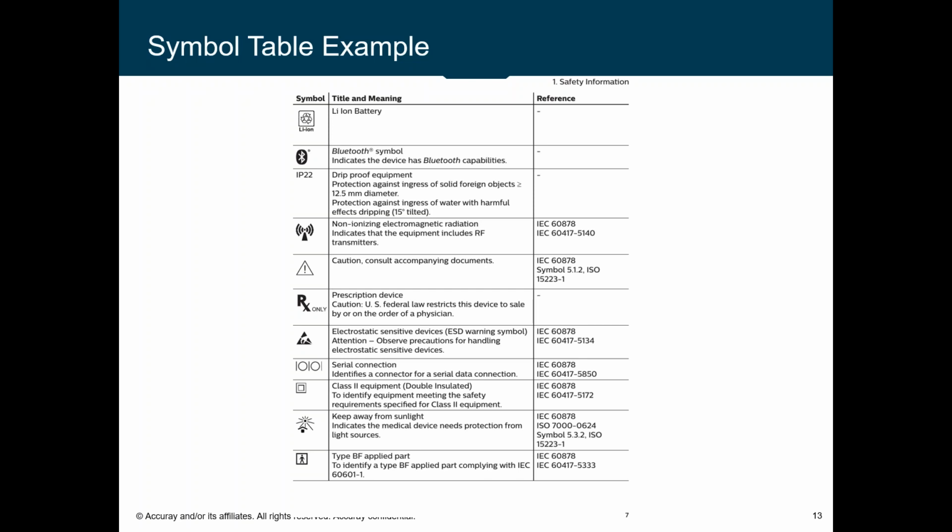Well, you have to do that, right? You have to define. Okay, I think I'm not quite understanding the question, but let me see if I can answer this. You don't have to use the symbols. It's not a requirement to use the symbol, but if you're going to use a symbol, you really should use a harmonized symbol, which is out of 15223. If you're not using a harmonized symbol, then you have to define it on the label itself, which then requires translation.